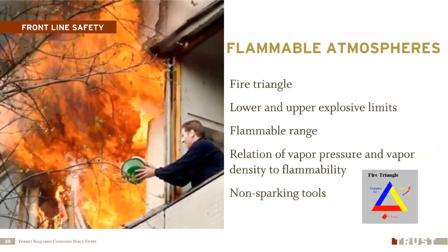The next thing we measure is the percent of the LEL, or lower explosive limit. This is for flammability. As we use flammable materials, or maybe there's naturally occurring methane in a sewer manhole, those can cause fires or explosions. We're going to measure that, and if your meter reads over 10% of the lower explosive limit - the concentration at which it can support combustion - your alarm will go off and you need to get out of there. Why do we do it at 10% and not 50% or 90%? Because burning to death is a really bad way to go, and things change quickly in a confined space - it's concentrated. So at 10%, that means get your butt out of there.